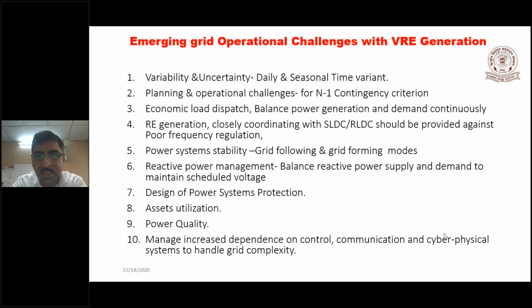Since there's a drastic change in the current and voltage parameters of the system, I have very reliable protections based upon current and voltage. Distance protection and current protection are there. They can detect the fault and clear the fault effectively. So protection has become such a reliable component of the power system that we are not facing any problem. But as I told, this whole operation is only possible when there's a drastic change in the current and voltage. But just think of a system where you have only renewable-based generation. In that case, if you apply any fault, you will not see much increase in the short circuit current.